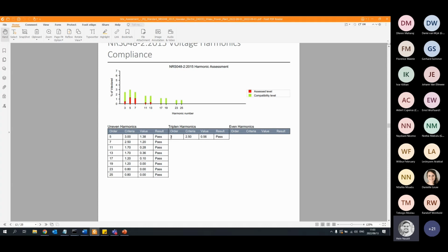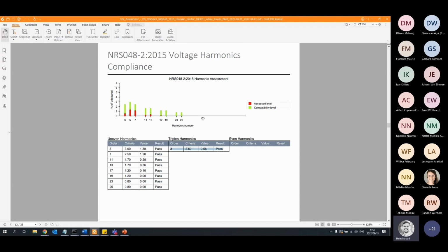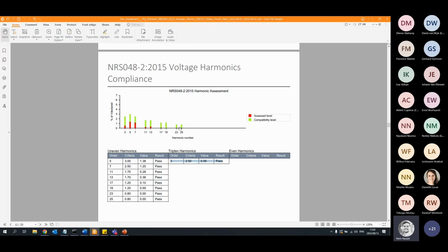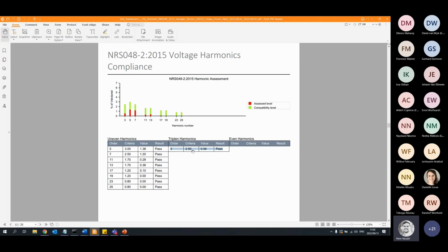Yeah, so the only reason why we're not showing the other harmonics is because at this voltage level, there isn't any limit or level specified for those harmonics. So we only show the ones that there are actually limits for. But on Osprey Pro you can do a harmonic spectrum graph that shows you the other harmonics as well.